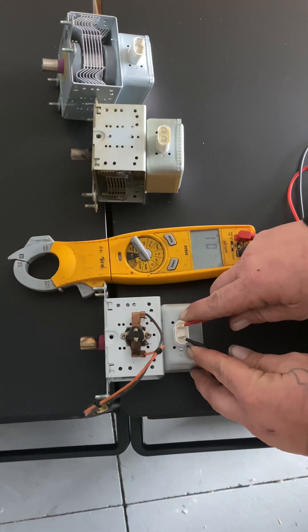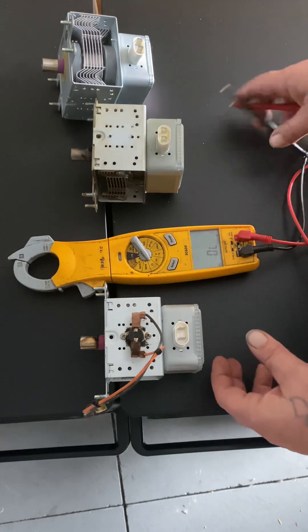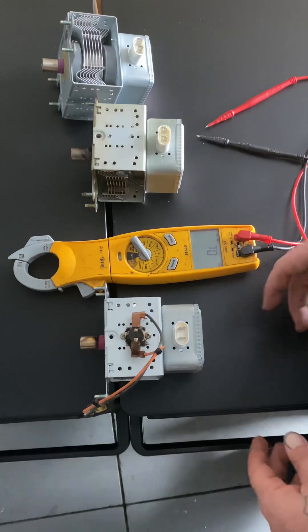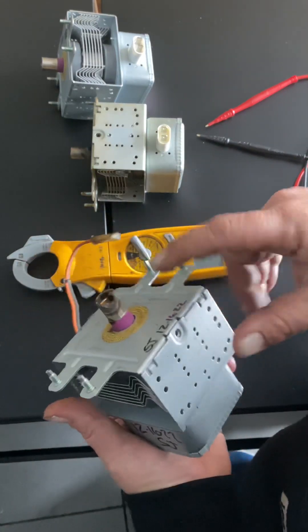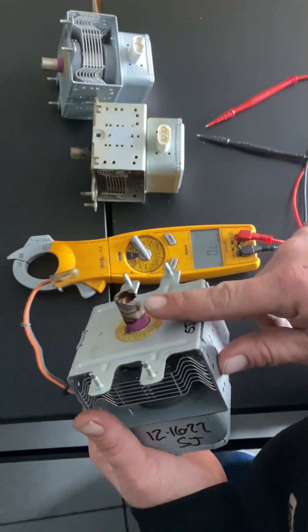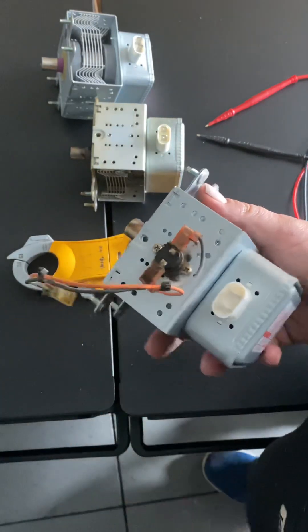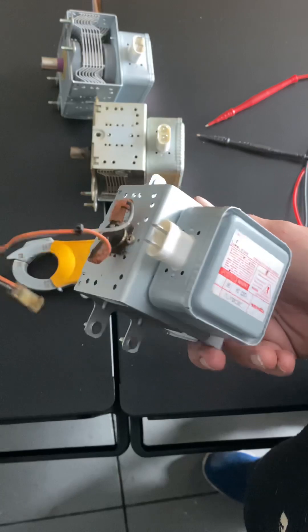It goes 0.1, 0.0. All right, so see we got three magnetrons here. What I want you to really look at is the damage on the antenna of the mag. See that damage? This magnetron actually passed.